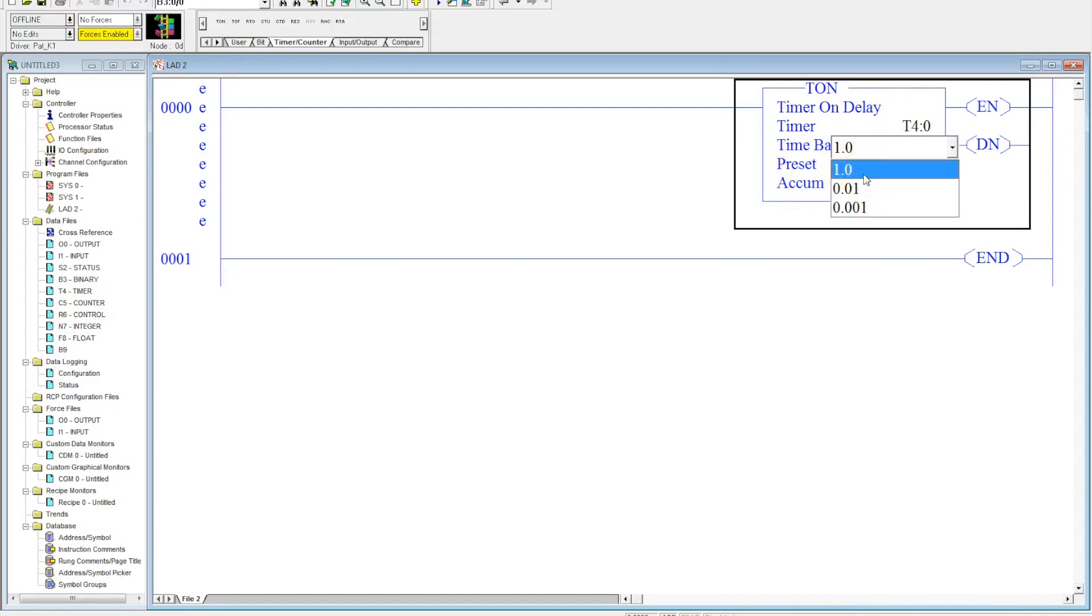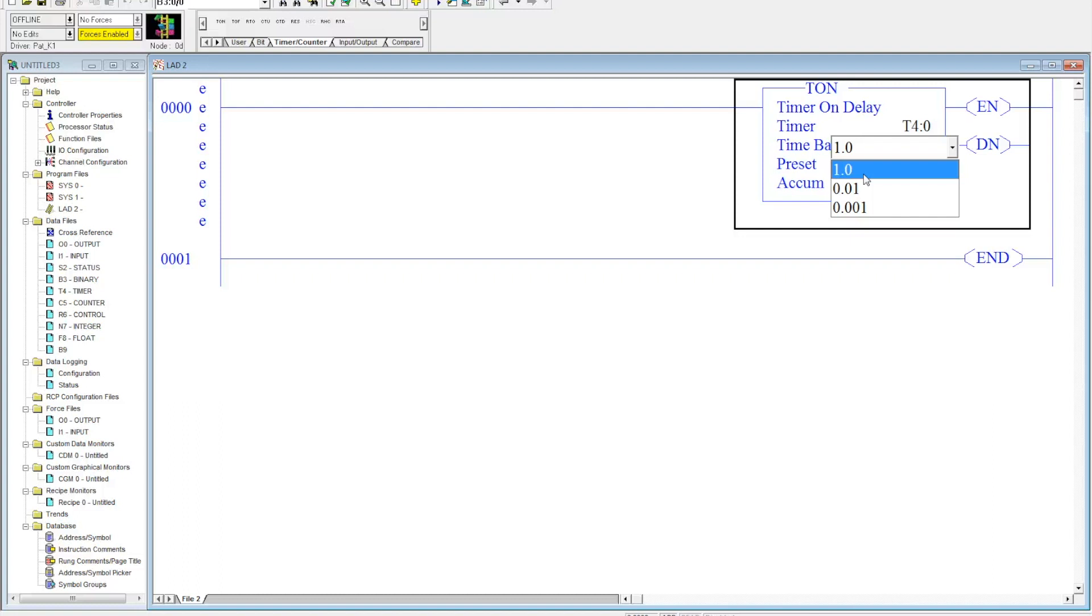We can make it at one, and that just means you would take whatever is in your accumulated value and multiply it by one. So if you need two minutes, that'd be 120 seconds. You would put 120 in your preset value.